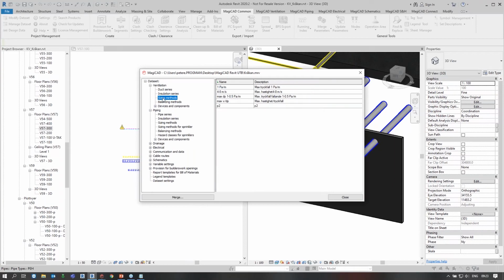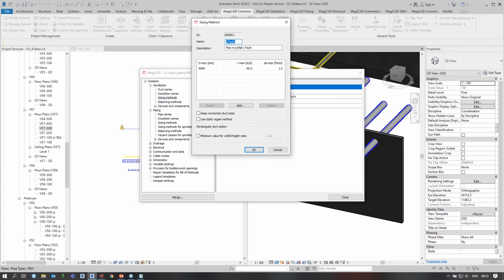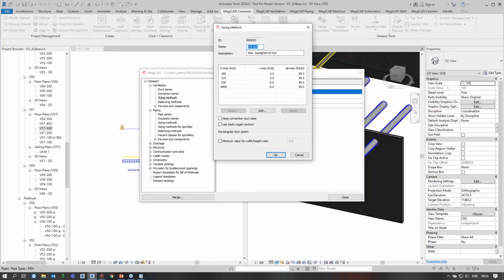And of course, how do you want to size your ducts, or how do you want to size your pipes? I'll show it for the duct, it's kind of the same. I can select here: do you want to go after just some Pascal per meter? So for all duct sizes up to 9,999, I don't want to use the velocity in this case. I want to use the pressure drop. But I can also create that, okay, like with the pipe insulation, with this one I allow the area of the duct to be between 0 and 160. Then I want to have a maximum of 4 meters per second. And so I can now create my own sizing methods.